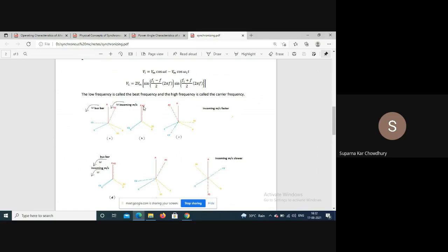For this condition, see what the voltages across the lamps are. One lamp was connected between A and A1, so that lamp has a small voltage and will glow dimly. The other lamps were connected between B and C1, and between C and B1. So for this figure, all three lamps are glowing, but the voltages available are different, so the amount of glow will be different.